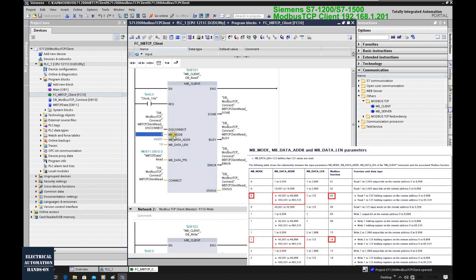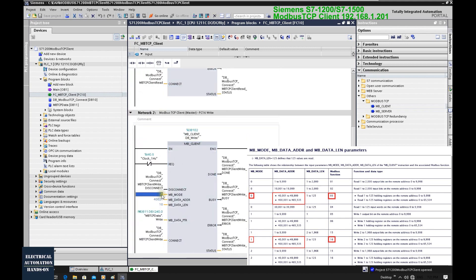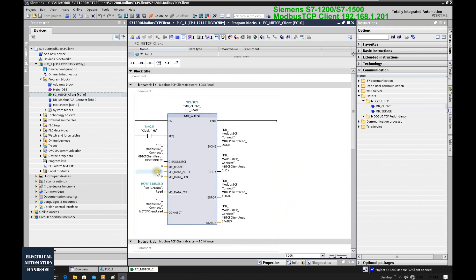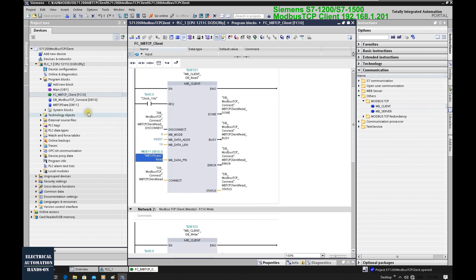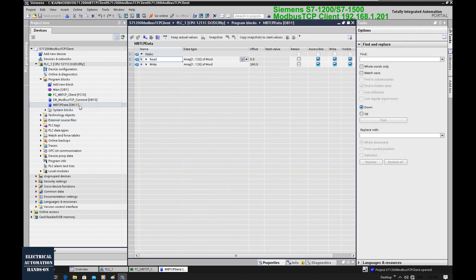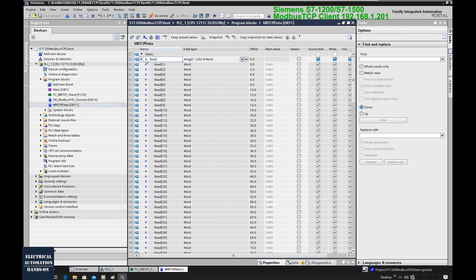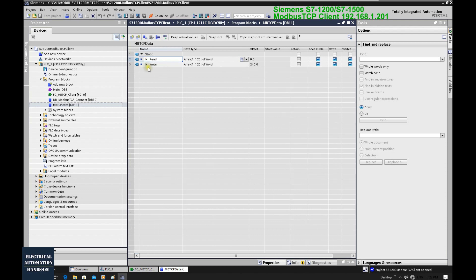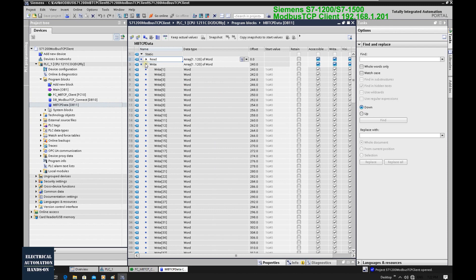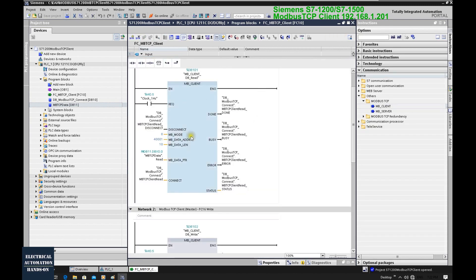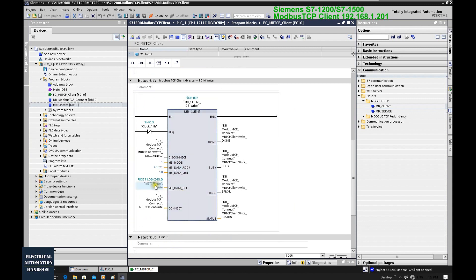The first function block has Modbus mode set to 0, meaning the client will read data from the server. The second function block will write data from the client to the server. For the read side, the Modbus address starts at 40,000 with a length of 10. The PLC buffer comes from DB11. In DB11, I set up two arrays: one is a read buffer and one is a write buffer, both with word units. The read function block uses the read buffer, and the write function block uses the write buffer from DB11.